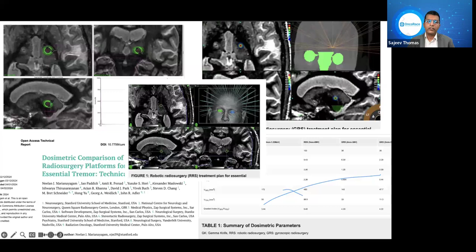If you look at the technology of both systems, here we have the gamma knife frame with the sectors, and here we can see the ZAP-X, which also has a comparable SAD and the features of the focal spot size. The focal spot size is 1 mm and 1.1 mm, where the energy is 1.25 for the gamma knife, and here there is an energy of 3 MeV. That is 3 MV. 3 MV is the correct one.